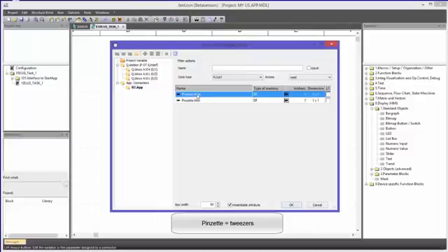The variable reset_min_max cannot be found here because, 1, the filter of the data type float is active and the reset variable is of the type bit_byte, and 2, the filter for read is active. This filter function is a default setting, as we want to connect the attribute to an input of a function block, which has a data type float. The input switches the filter to read, and the data type of the input is float. And that is why the filter is set to read and float.